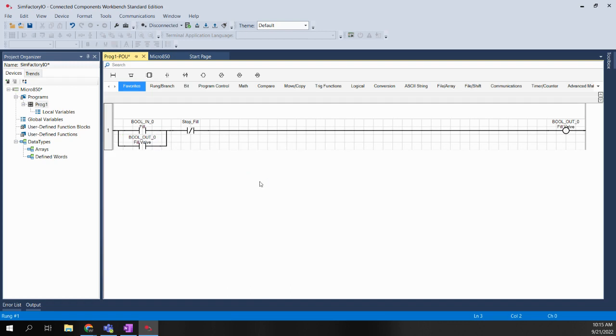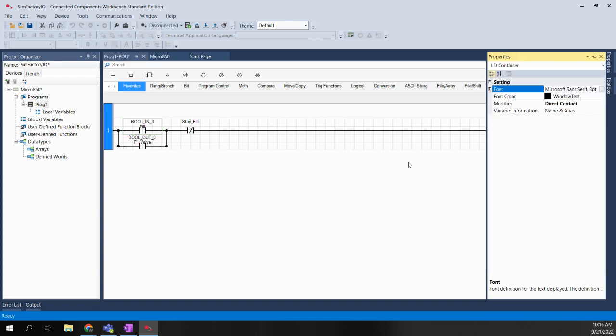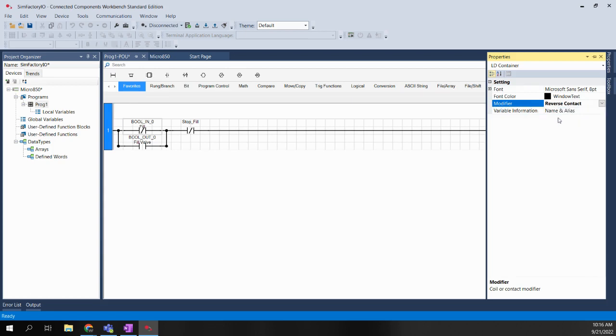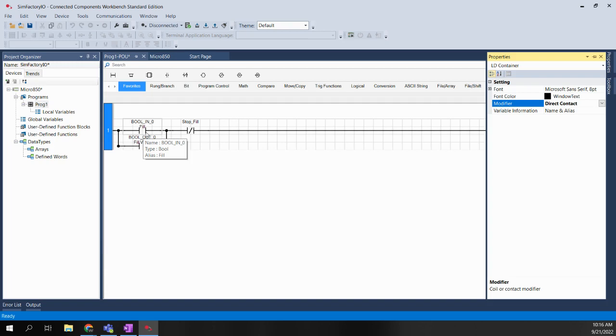The answer is yes — it's just a little bit of a hidden secret. If I click on this contact and say I want to make it a normally closed contact, I can right-click and choose Properties. That'll open up the properties pane on the right-hand side. It wasn't really intuitive because they use the term 'modifier' and then 'direct contact.' If I click in that box, a pull-down menu appears and I can choose 'reverse contact.' When I do that, the contact changes to normally closed. If I go back to direct contact, it goes back to normally open.